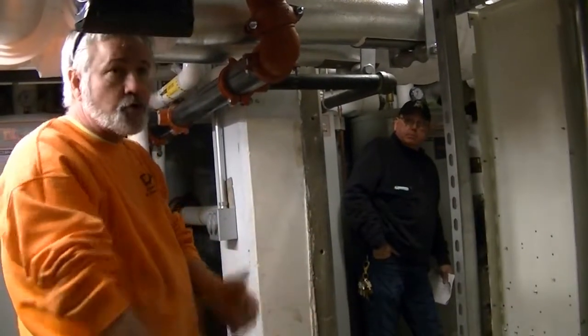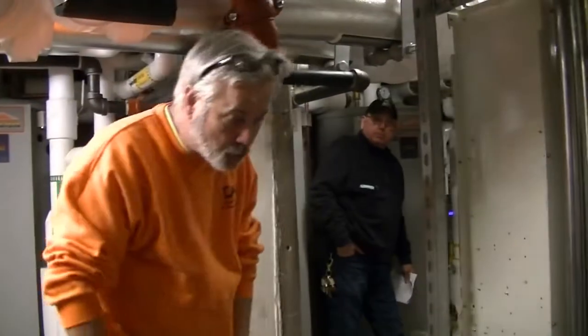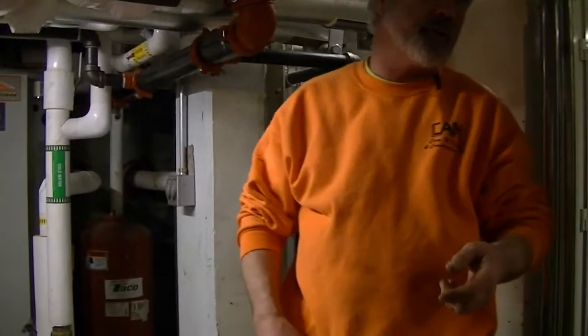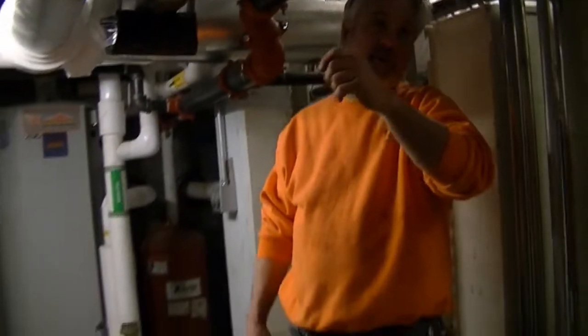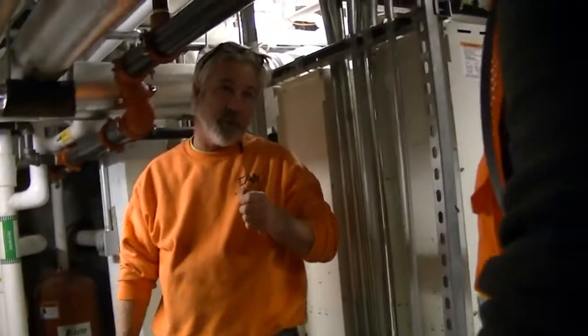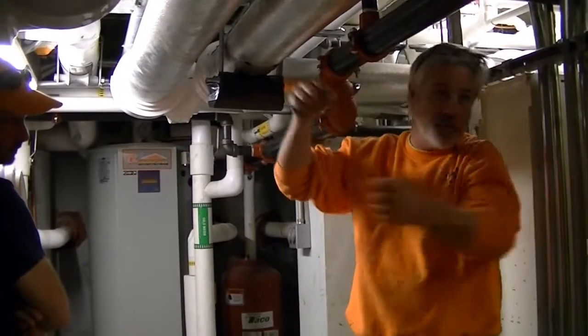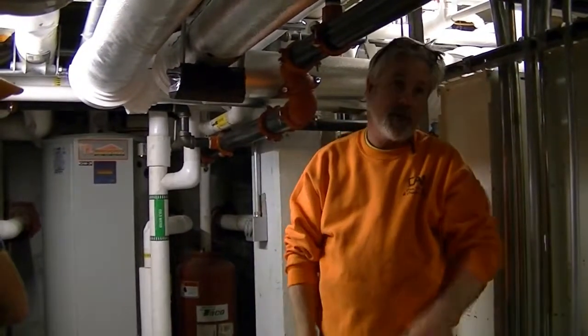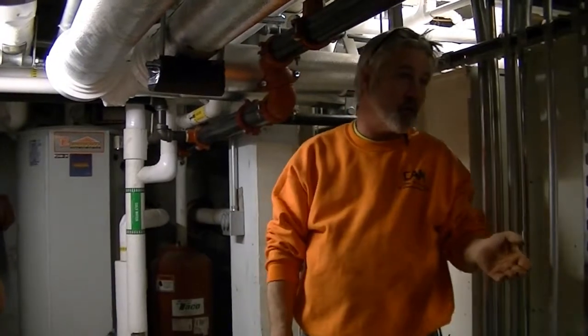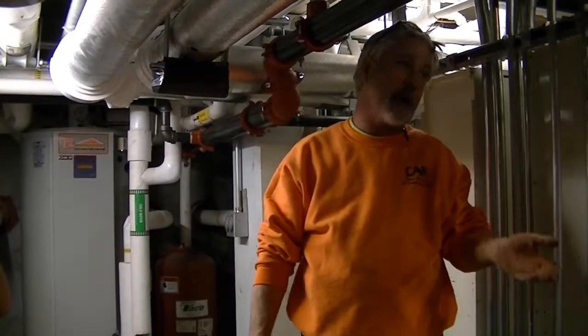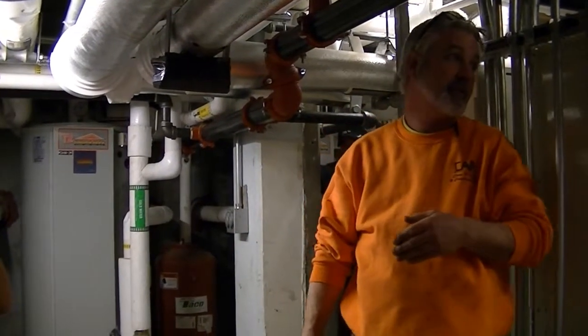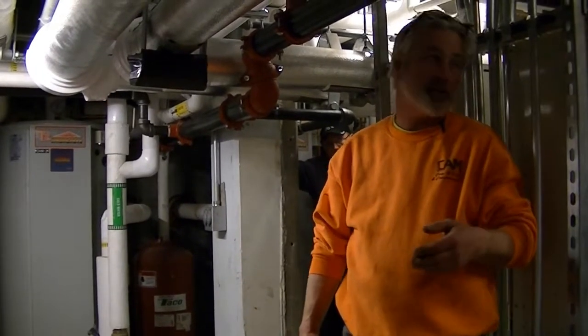Well, if the control failed, what you would have to do is, there's a set of releases on the three-way valve. You'd have to go to the Viessmann panel and unplug the harness for the three-way valve, hit the plungers, remove the valve, and leave it in that position. Now you've got no control over the temperature of the hot water going out. It's going to be whatever the boiler temperature is. Okay? That would be an emergency situation.